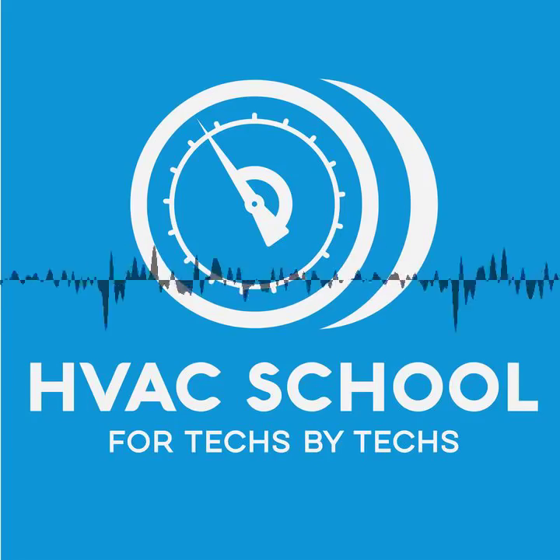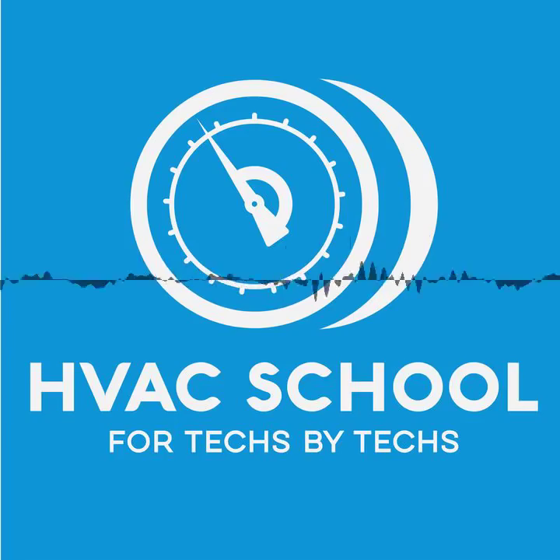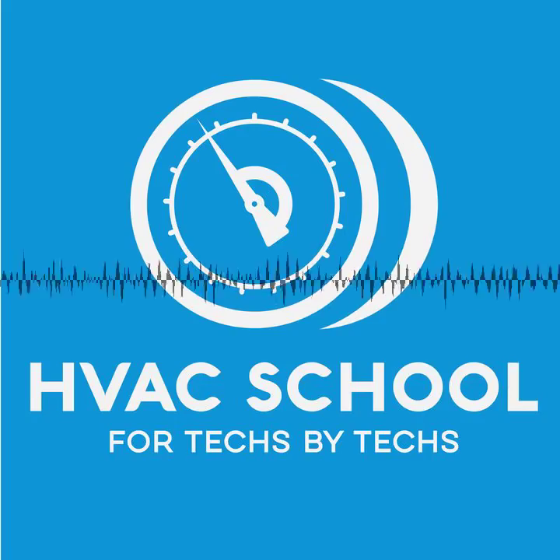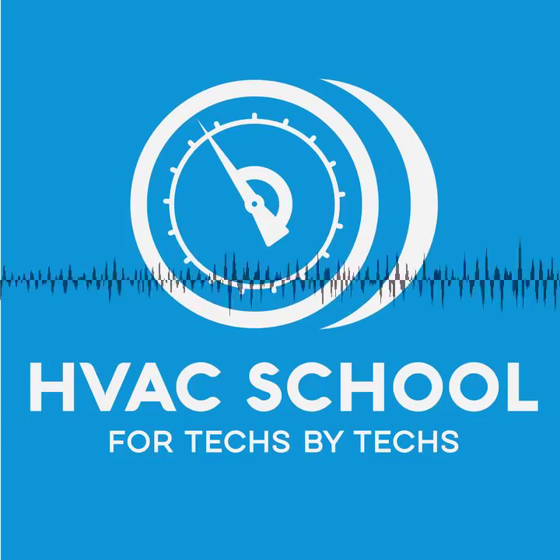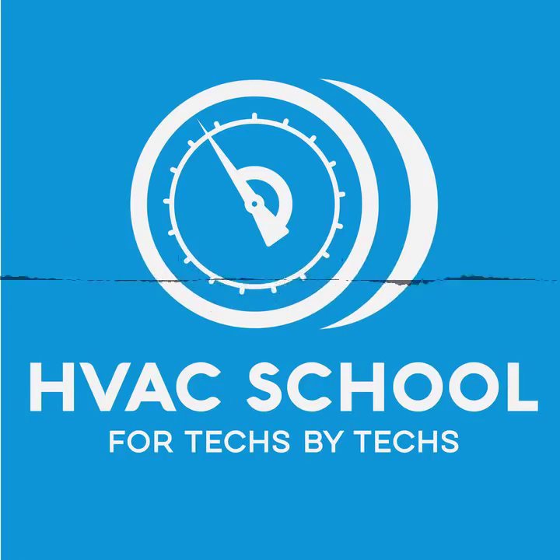What can happen there, like with an airflow issue, is that not only do you get the high compression ratio, which of course hurts your capacity, but it hurts your compressor, because now you're not moving as much gas as it was originally designed to move, and so the compressor starts heating up. And that also confuses people some, how the compressors actually get hotter and work harder at cold temperatures than at hot temperatures. So as a general rule, the compressor will be operating cooler and be happier when it's 95 outside and you're in air conditioning than when it's 5 outside and you're in heating.